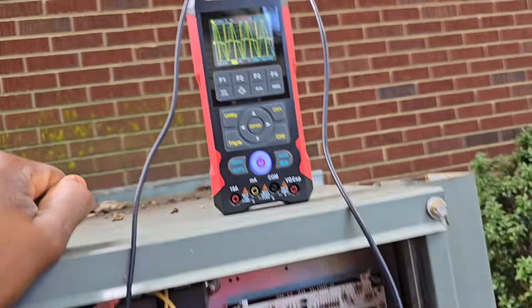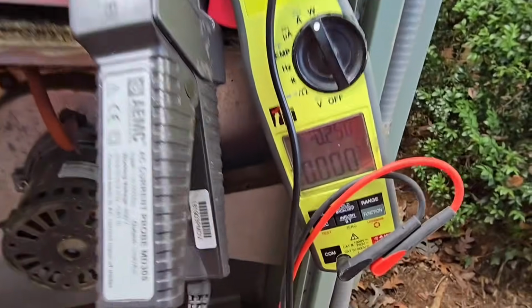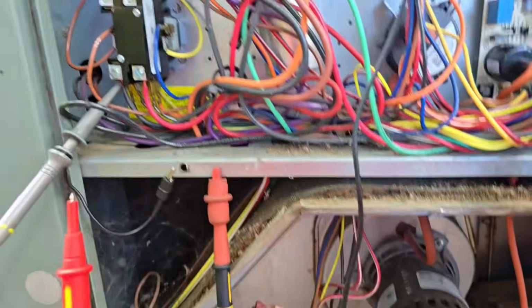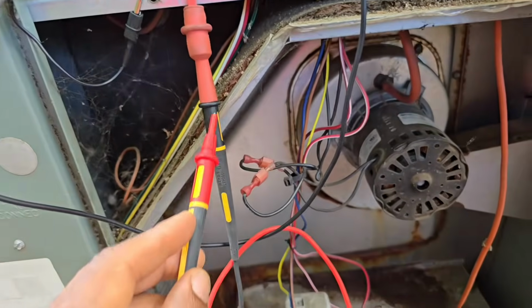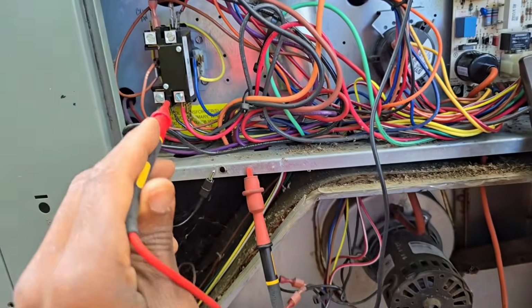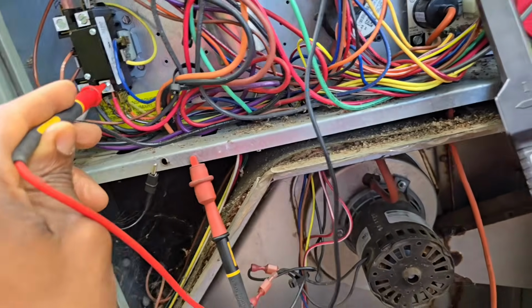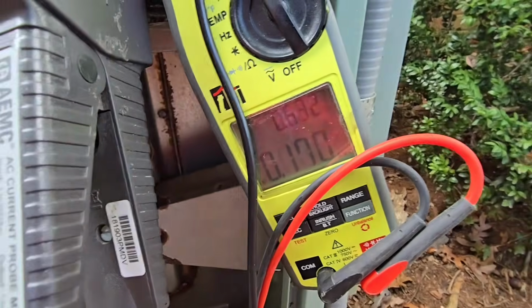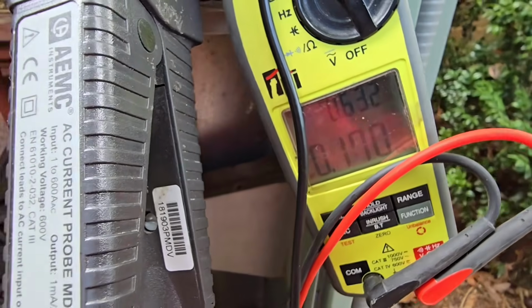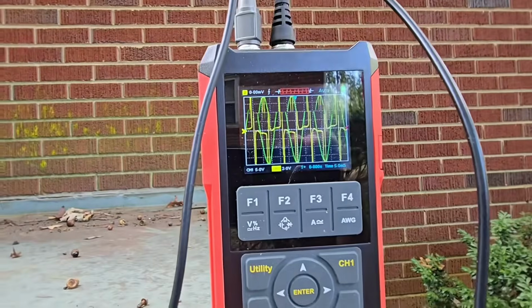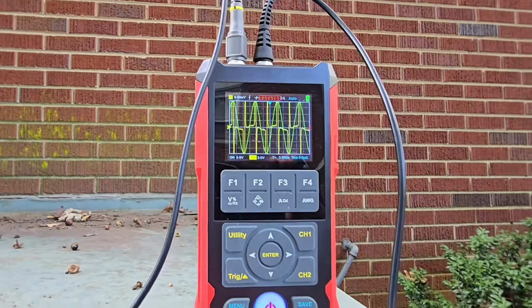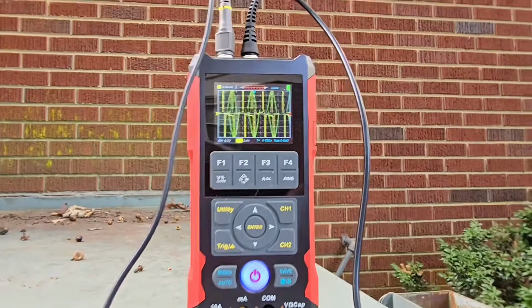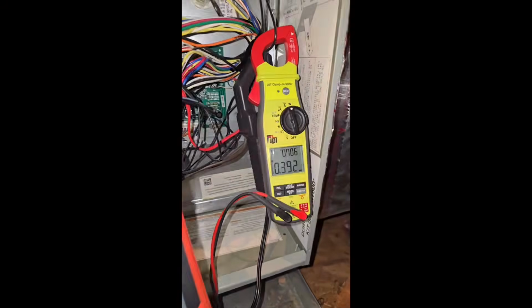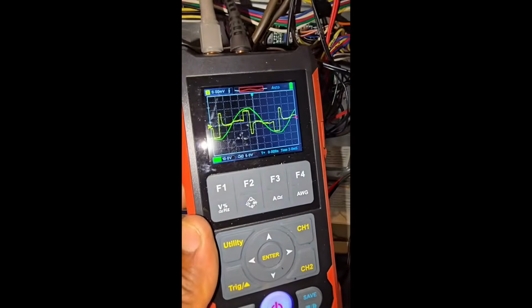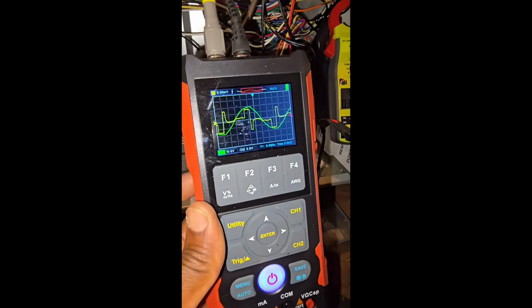And that's because this is going to be an ECM motor, okay? And we're going to take a look and see what our power factor registers as well. I've got one leg on the ground, and I'll take the other to one of the legs of 240. We can see our power factor is 0.63 at 170 watts. So that's what a 0.6 power factor looks like, that's a 0.7 power factor, and that's a 0.7 ECM waveform.